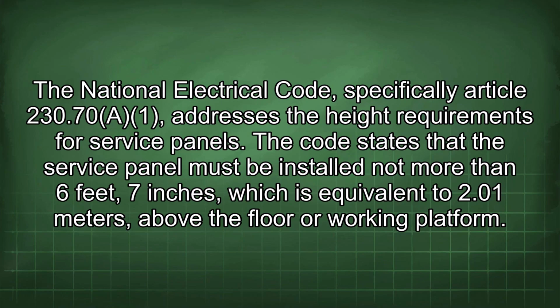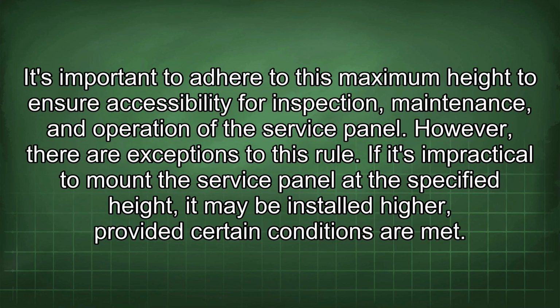The National Electrical Code, specifically Article 230.70(A)(1), addresses the height requirements for service panels. The code states that the service panel must be installed not more than 6 feet 7 inches, which is equivalent to 2.01 meters, above the floor or working platform. It's important to adhere to this maximum height to ensure accessibility for inspection, maintenance, and operation of the service panel.